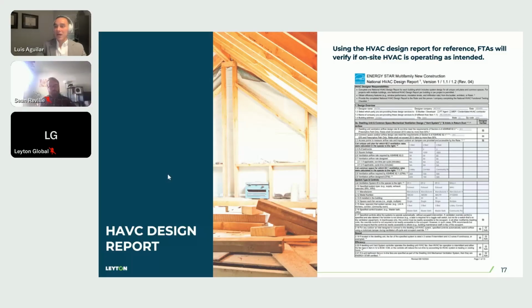So we're looking at design airflow at maximum speed. If it's a multi-speed, we have the low, medium, and high speeds, as well as design airflows for each zone. Each home could have multiple different zones, those being the bedroom, dining room, living room, things of that nature. So there's a specific amount of airflow that must go to each room. We want to make sure that we're taking a look at all this and familiarizing ourselves with how it's intended to operate before we go on site.